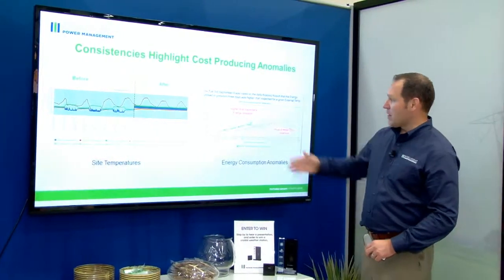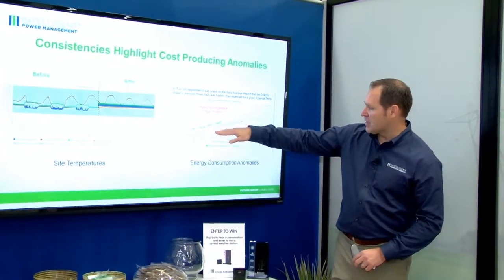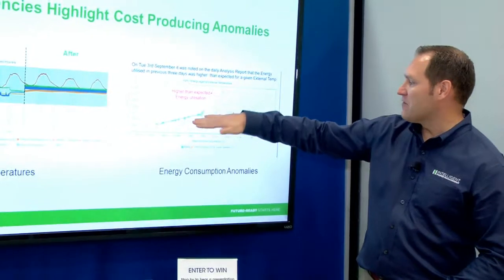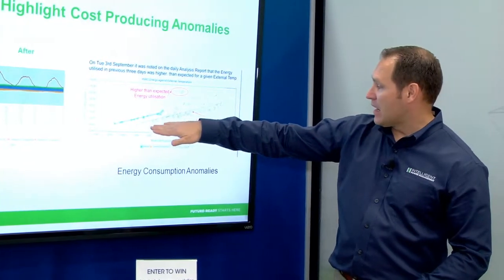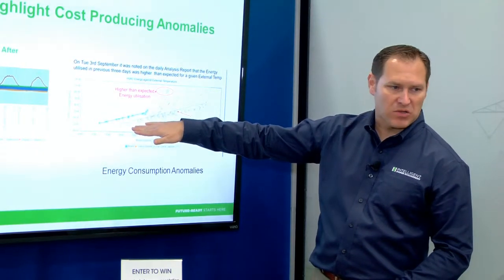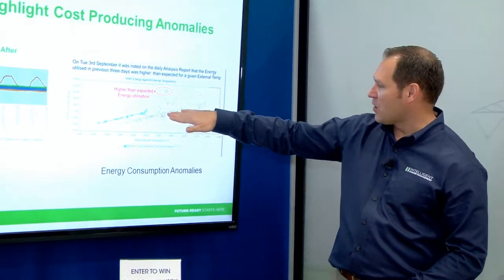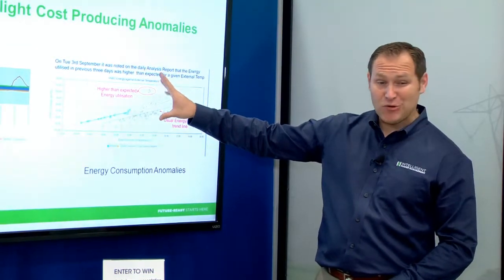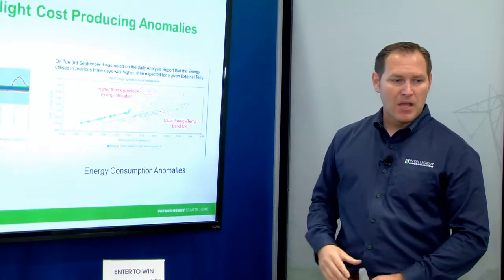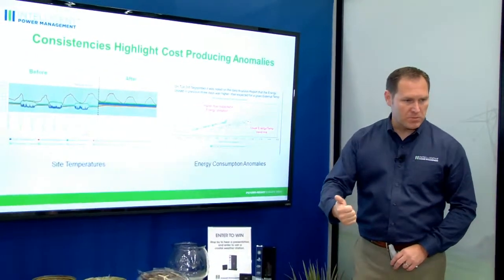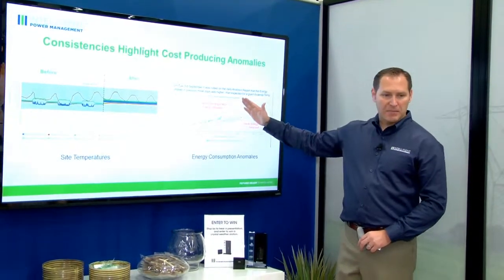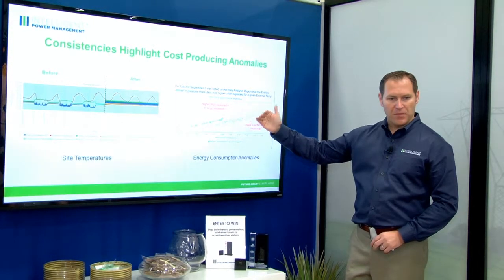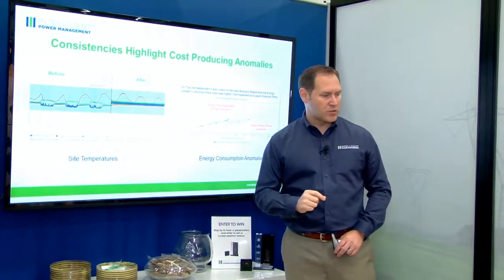Over here on the right, this line shows the CDD — cooling degree days — of how a site operates, and this gold represents HVAC consumption based on certain points in time. It's pretty consistent, following that line. But all of a sudden, out of the blue, for this particular site, energy spiked from roughly 70 kilowatt hours up to 112 kilowatt hours — a significant increase in energy consumption, equating to about $5 a day in additional energy cost. Because no alarm thresholds were met — no temperature alarms, no power outage alarms — nothing was sent back to the NOC.